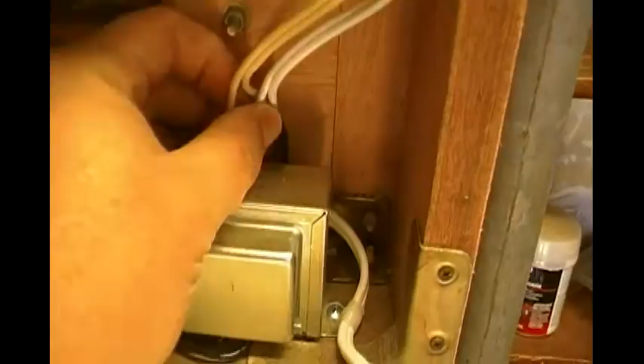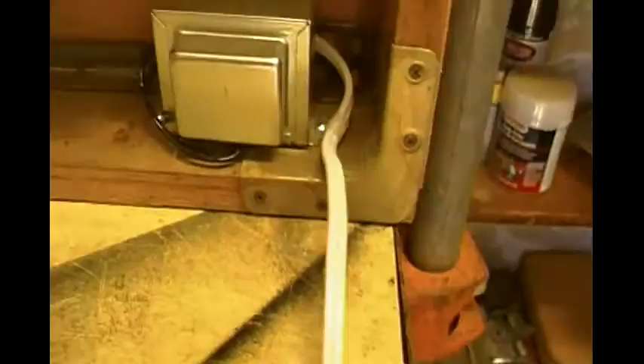As you come down, you can see this wire right here that comes up into the bottom of the box is the 24 volts, or 25 volts in this case, that powers the solenoids. I have the wires tied off down to the side. We're going to come down to the transformer. You can see we've got 4 leads coming off the transformer, 2 and 2, and then the power here is for the 110 volt plug-in. This is a transformer, the new one that hasn't been used.